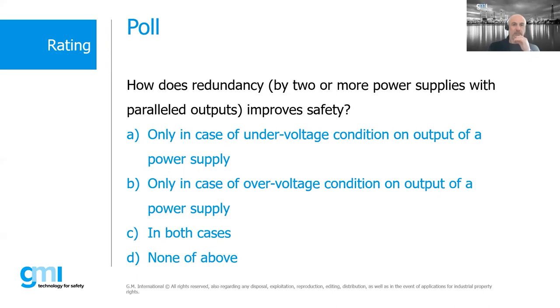Okay, let's stop it. So we say that by applying internally to each power supply redundant protection against the overvoltage condition, reducing the probability that the overvoltage happens, the redundancy can of course protect the output of the power supply. So in case of overvoltage, of course, that redundancy improves safety.